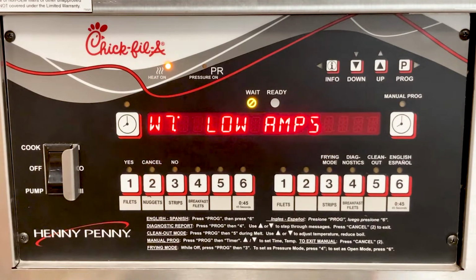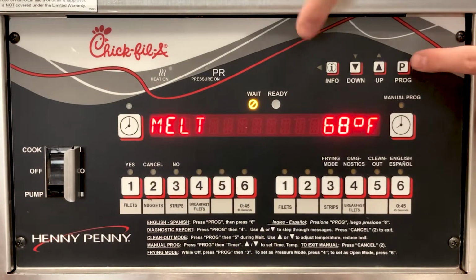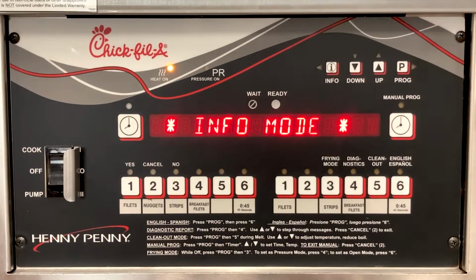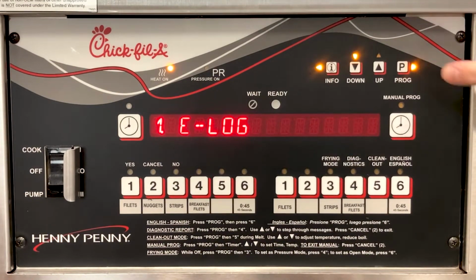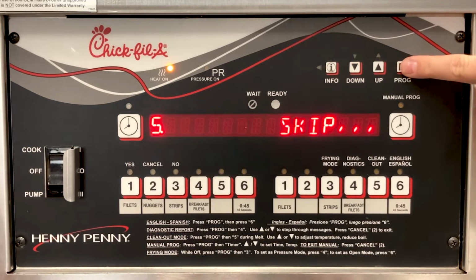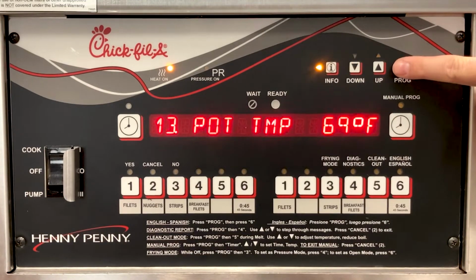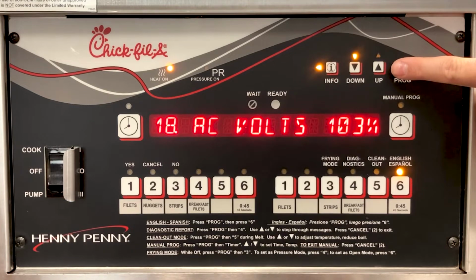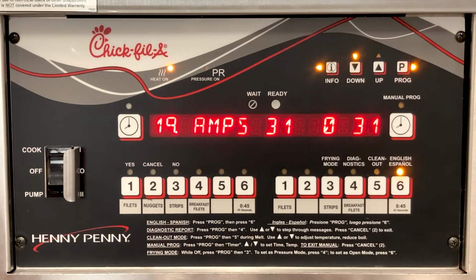To start troubleshooting the W-7 or E27 error, take special note of the amp draw reading on the control for each leg that was given when the error code occurred, or go into info mode by pressing and holding the I and P button at the same time. Then use the P button to scroll over to amps and check the current amp draw reading while the unit is heating. The importance of this reading will help you determine which troubleshooting steps to take.